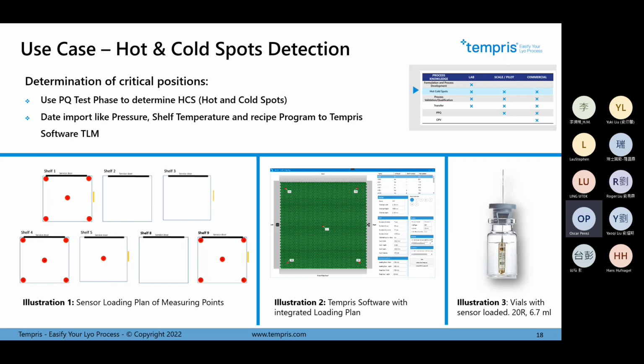I also want to introduce that the software will very soon have an application that allows you to configure in our software all the measurements, or all the information about your freeze dryer chamber and also about your product, as we will see later. The reason is that when we have the cycle done and we want to export the log file report, we will also be able to show this information. Where was the location of sensor number 1? It was in shelf number 1, for example, in the corner right from the service door, or in the center of the shelf. So all the information will be in the same document to make the post-analysis of all this data easy, for validation runs, or also for all the batches that we are measuring.